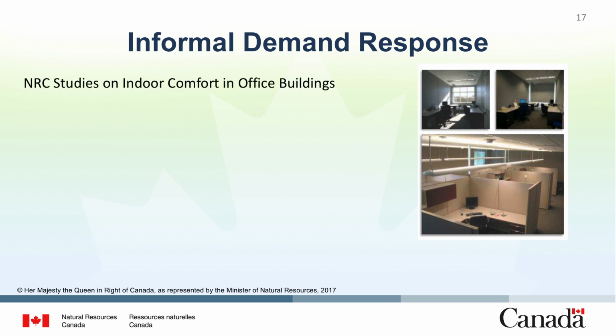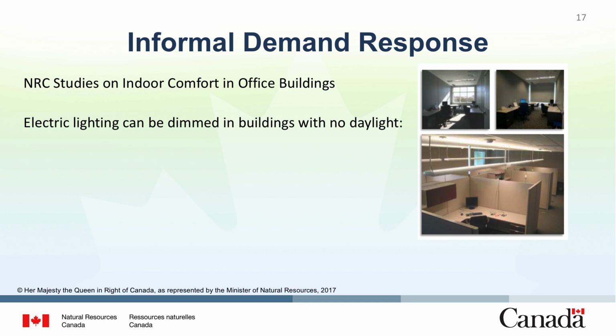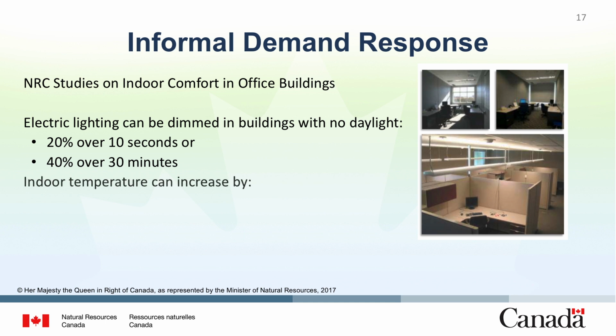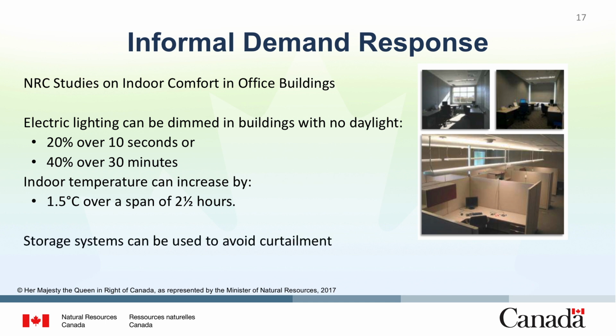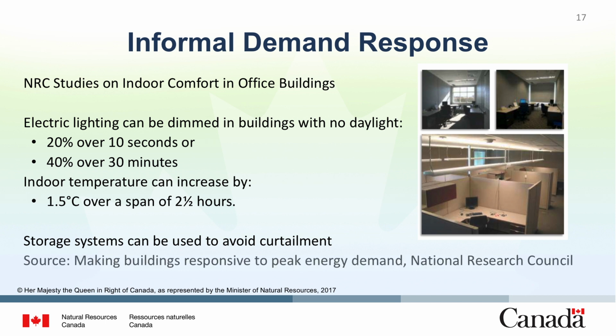The National Research Council embarked on a series of studies to define reasonable times for service curtailment. The results of this study showed that electric lighting can be dimmed without negatively impacting the building occupants 20% over 10 seconds or 40% over 30 minutes in buildings with no daylight. The study also shows that indoor temperatures can increase 1.5 degrees over 2.5 hours without impacting the building occupants. These two measures are simple ways that building occupants can reduce demand during peak periods. In more advanced systems, HVAC service curtailment may be avoided by using storage systems or by providing overservice prior to a DR event, pre-ventilating to create indoor air with low levels of pollutants, allowing for a reduction of ventilation during DR.